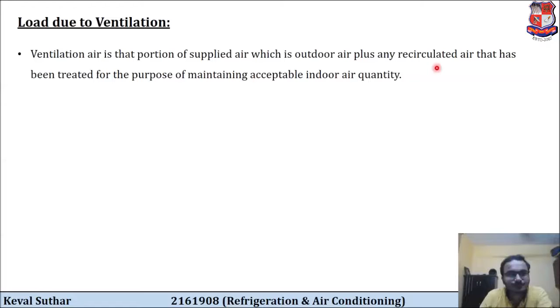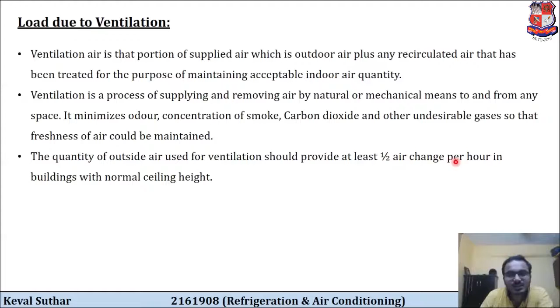Ventilation is the process of supplying and removing air by natural or mechanical means. So here we are supplying as well as removing the air by means of natural or mechanical means to and from any space. It minimizes the odor, concentration of smoke, carbon dioxide and any other undesirable gases, so that the freshness of air could be maintained. So this is related to comfort air conditioning. The quantity of outside air used for ventilation should provide at least 1/2 air change per hour in buildings with normal ceiling height.